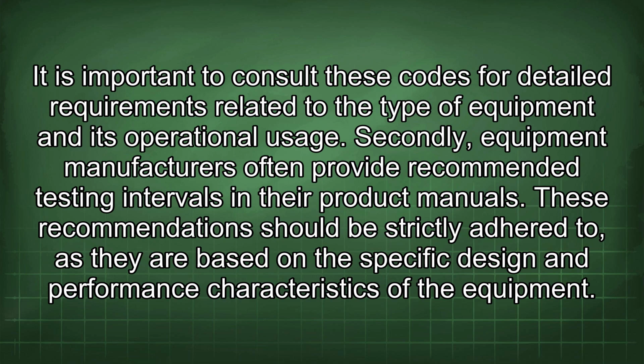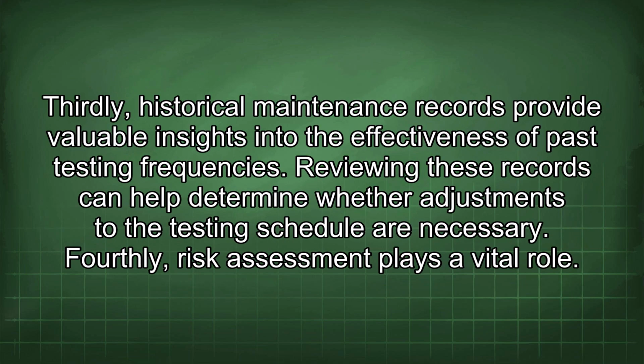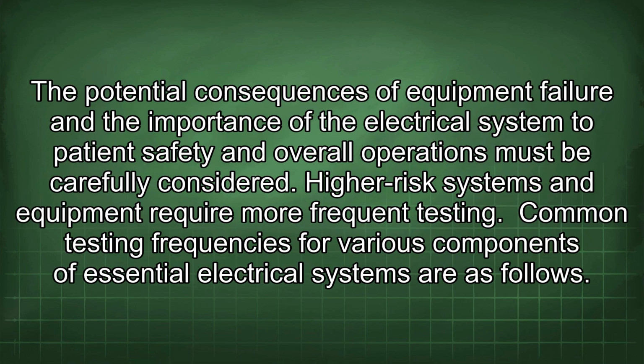Secondly, equipment manufacturers often provide recommended testing intervals in their product manuals. These recommendations should be strictly adhered to, as they are based on the specific design and performance characteristics of the equipment. Thirdly, historical maintenance records provide valuable insights into the effectiveness of past testing frequencies. Reviewing these records can help determine whether adjustments to the testing schedule are necessary. Fourthly, risk assessment plays a vital role. The potential consequences of equipment failure and the importance of the electrical system to patient safety and overall operations must be carefully considered. Higher-risk systems and equipment require more frequent testing.